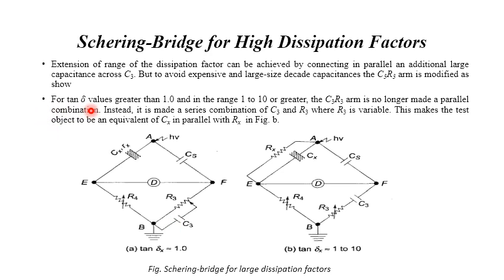Whereas in the case of tan delta greater than 1, in the range from 1 to 10 or sometimes greater, the arrangement of R3 and C3, the slide wire we used, is no longer made as a parallel combination. Instead, what we are doing is connecting R3 and C3 in series, but this makes the test object equal to Cx, which is in parallel with Rx. It means that in place of the parallel R3 and C3, we are making Rx and Cx connected in parallel.